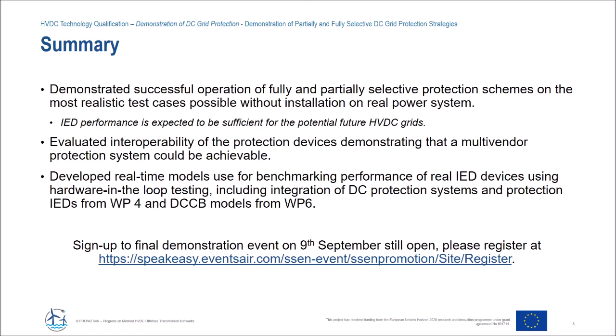So overall for the work package, it demonstrates successful operation of all the different types of protection schemes: fully, partially and non-selective. Through all that, the IEDs performed as expected and are sufficient for potential future HVDC grids. Interoperability was looked at in a number of different ways, by combining different types of breakers with different technologies, but also with the SuperGrid work starting to look at the use of IEC 61850.